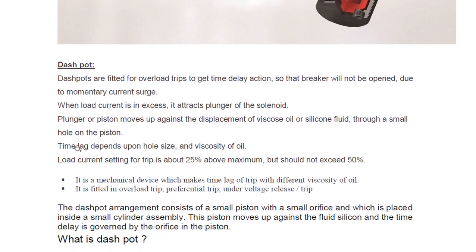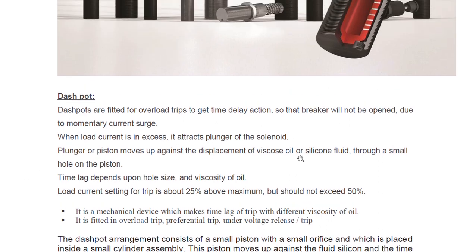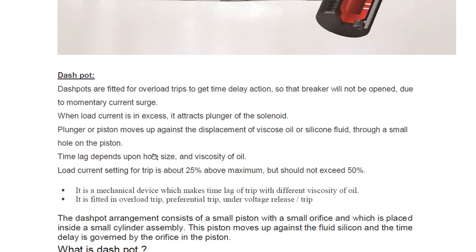The displacement occurs through viscous oil or silicone fluid via a small hole on the piston. The time lag depends upon the hole size and the viscosity of the oil — how much time delay there will be depends on the size of the hole and also on the viscosity of the oil.